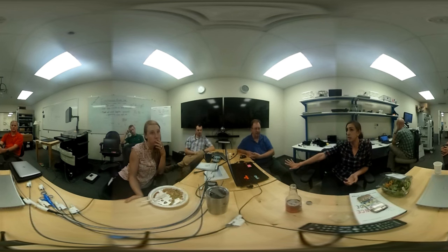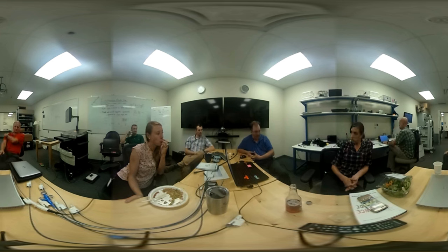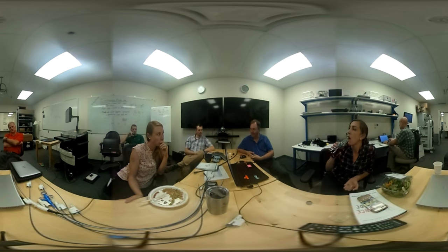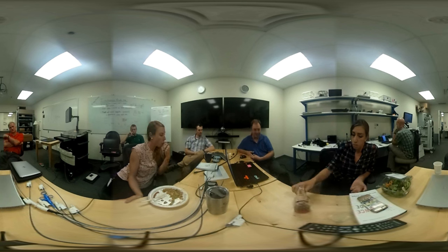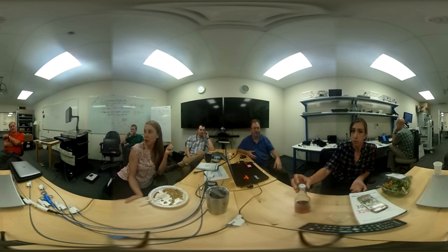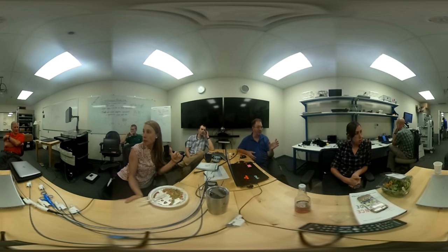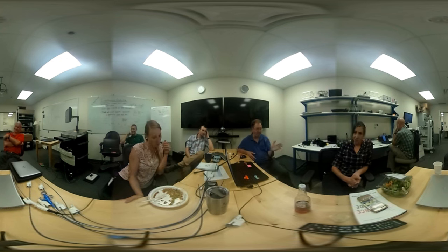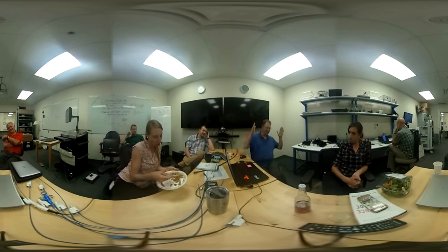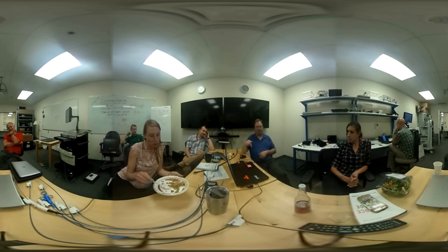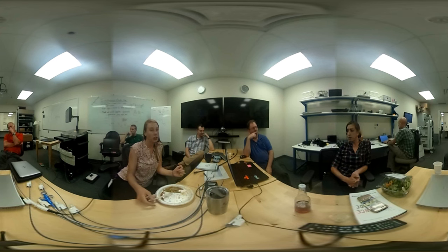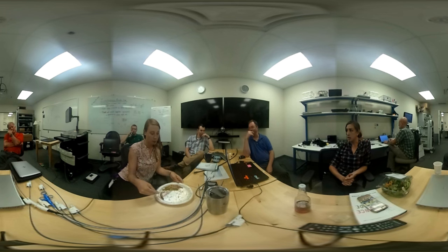I don't know. I was thinking, if you come back after you put it around or whatever, and the gain is a lot different, that tells me that we've kind of messed with our sensor. So that's why we wanted to test. But isn't the gain just plus or minus 10%, 0.4? Oh, but that's how much we, right, yeah. I was gonna say compare, not to the theoretical amount, but we calibrated this catheter, how different are we now from what we got before? The challenge comes in the variation of the system itself. We're trying to separate the variation in the original calibration. When you add in all of that, what's the threshold? Yeah, it would be something we'd have to develop, to see how reproducible it is.